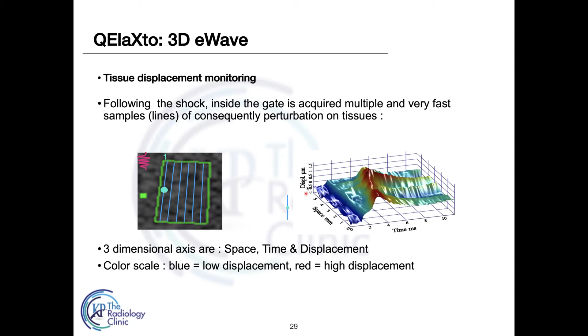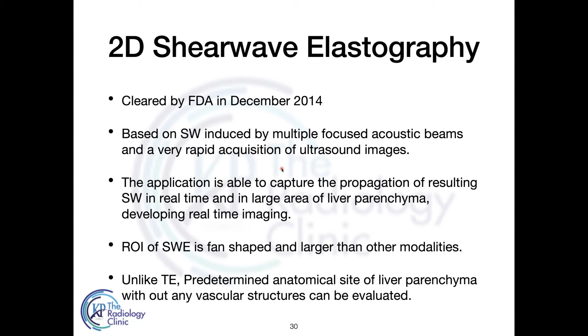Coming to 2D shear wave elastography, cleared by the FDA in 2014, it is based on shear waves induced by multiple focused acoustic beams and a very rapid acquisition of ultrasound images. The application is able to capture the propagation of the resulting shear wave in real time over a large area of liver parenchyma, developing a real time image. The region of interest is fan shaped and larger than in the other modalities. Unlike the fibroscan, a predetermined anatomical site of liver parenchyma without any vascular structures can be evaluated.